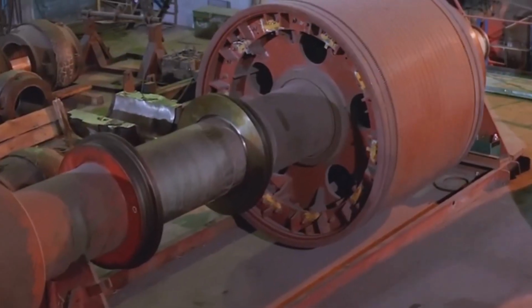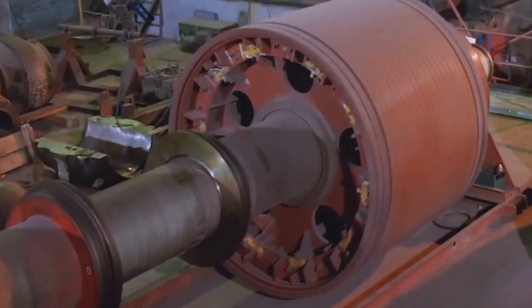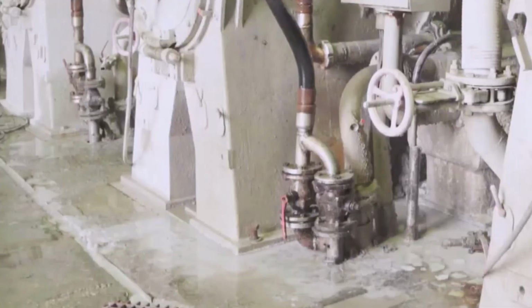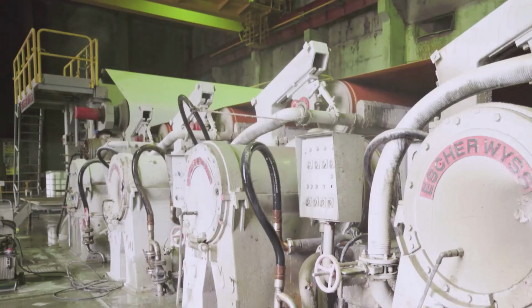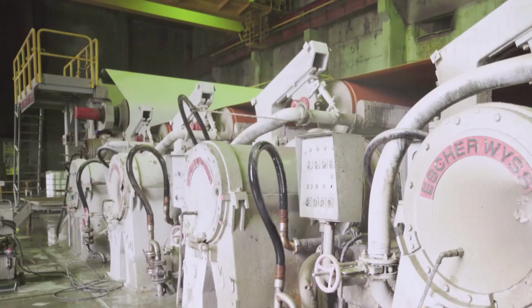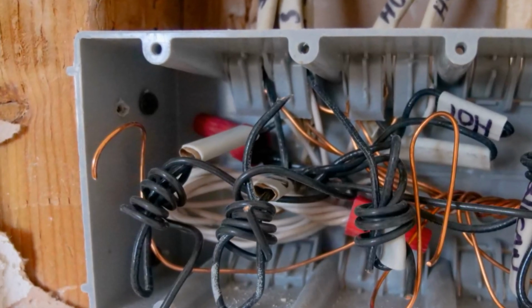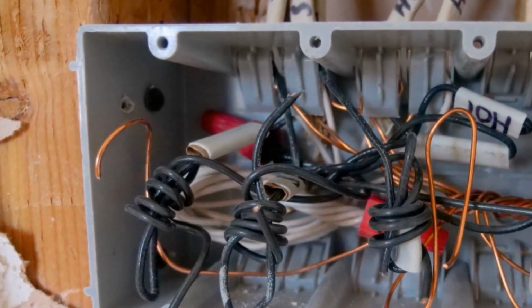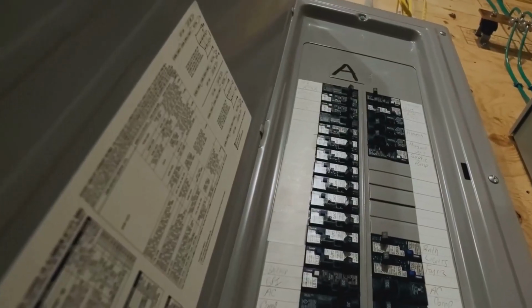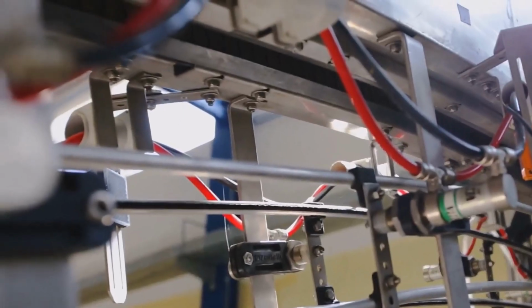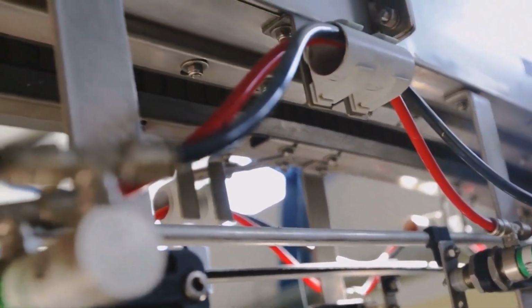Another great benefit is that delta systems provide a higher starting torque for large motors, helping them get up to speed quickly, which is crucial in many industrial processes. Another key advantage is that the delta connection does not have a neutral point. The system is made of just the three hot wires. This can be a benefit in balanced three-phase only industrial environments because it simplifies the wiring. You only need 3 conductors instead of 4, which can save on material and installation costs.